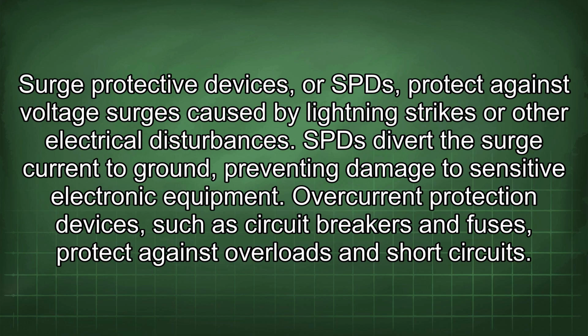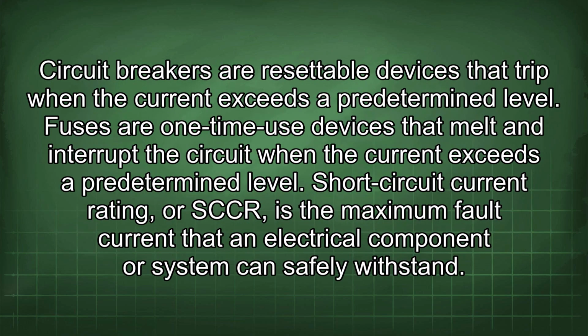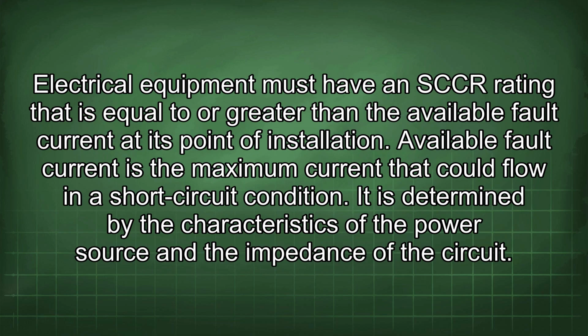Overcurrent protection devices, such as circuit breakers and fuses, protect against overloads and short circuits. Circuit breakers are resettable devices that trip when the current exceeds a predetermined level. Fuses are one-time use devices that melt and interrupt the circuit when the current exceeds a predetermined level. Short circuit current rating, or SCCR, is the maximum fault current that an electrical component or system can safely withstand.